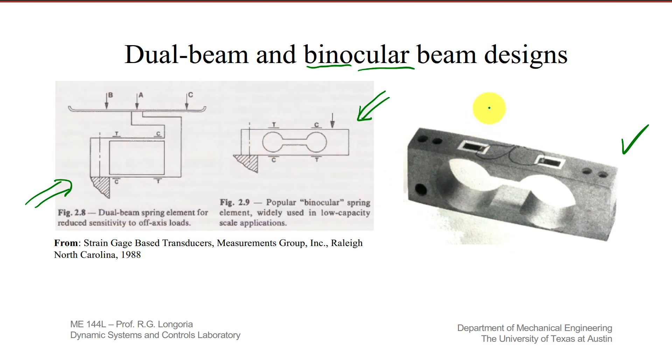Note, strain gauges are mounted right over these binocular sections. One strain gauge active along this axis, another one here. Now, how are those wired? Well, as you can see, when you apply this load down here, this gauge will be in tension, and this one will be in compression.